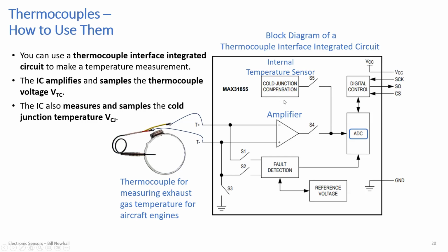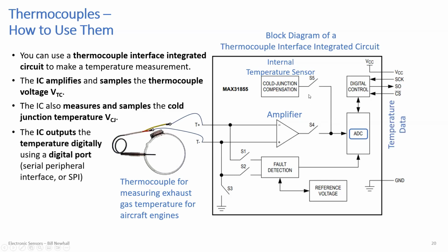There's internal temperature compensation, so it has a sensor built in, probably one of those silicon-based temperature sensors. The ADC switches between the amplifier output from the thermocouple and the internal temperature sensor so it can compensate. This IC outputs in a digital format, with digital control that's probably more than just control, but calculation, outputting serial data over an SPI bus for the temperature data.